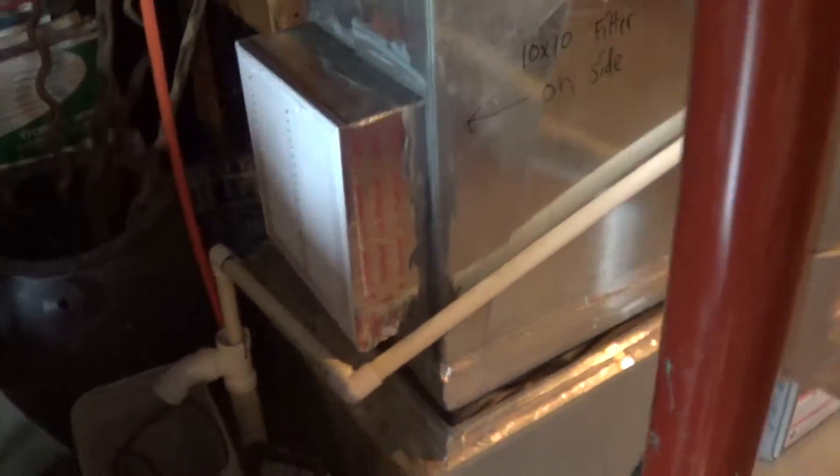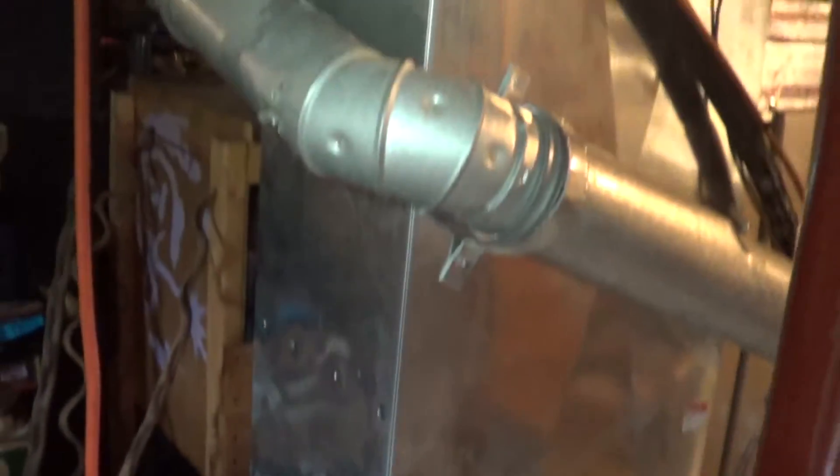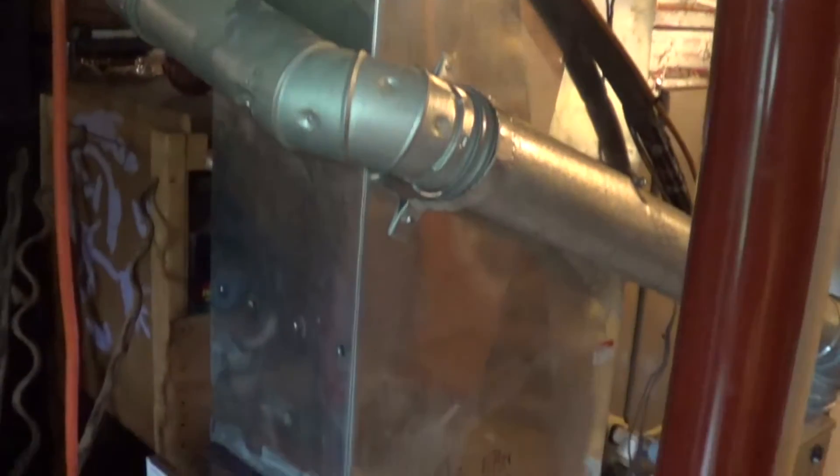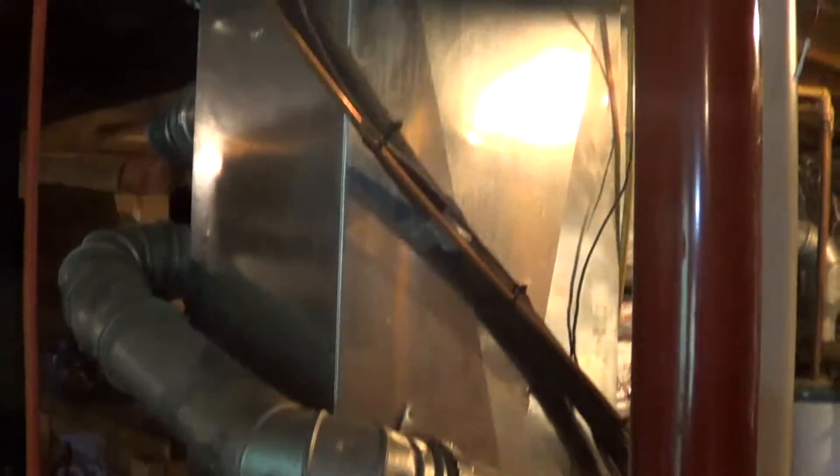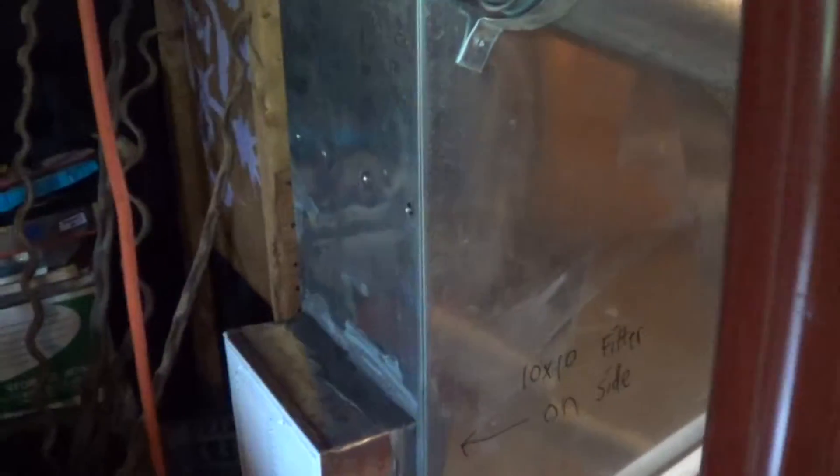I wanted to show an accurate way to measure airflow on this system install. We've got a nice straight run for the return air, and that's the most accurate because the air is going to be laminar with very little turbulence going straight down.